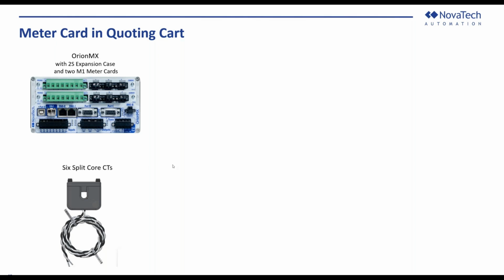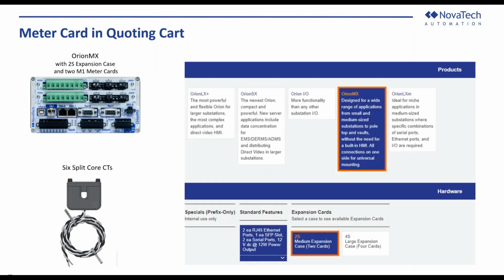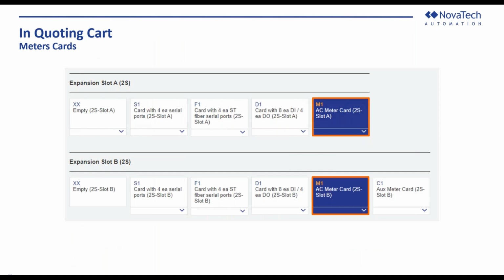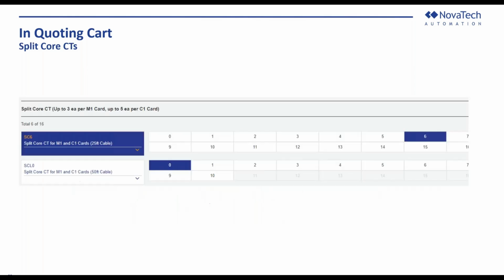If this is the box that you need, you can go to our quoting cart website, select the OrionMX, and then 2S, so that can accommodate two expansion cards. And then from there, you would choose AC meter card on slot A, M1, and M1. It doesn't have to be M1, M1. You can select the aux meter card too. But for our example, we're showing 2 M1 cards in the 2S slots. And then we would choose the split core CTs, which was 6 of them.